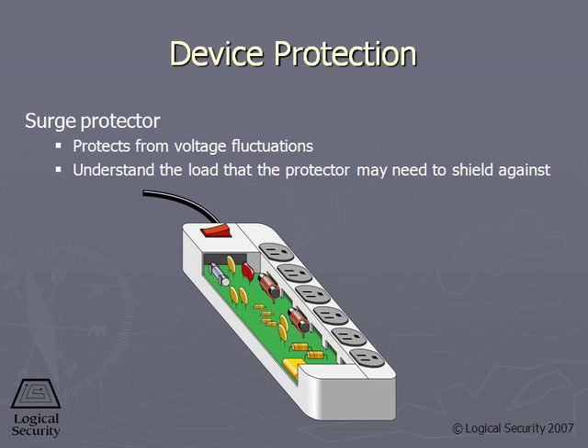And then again, of course, don't have power lines and data lines close to devices that cause interference. We talked about this with the fluorescent lighting and the ballast and things along these lines. The device we see here is a surge suppressor. A surge suppressor knocks down spikes and high voltage situations on the electrical power. These do not have batteries and they don't provide supplemental energy. So they only provide in overvoltage situations, not undervoltage situations.